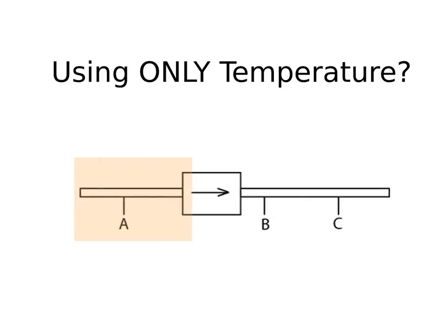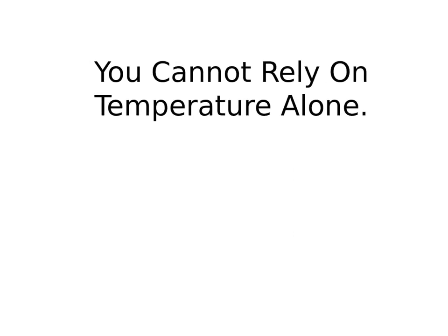If it's lower than 225°F, there's either a problem or that part of the steam system is not in service. Conversely, if the trap is hotter than expected, go to the downstream side and listen with contact ultrasound — you'd expect to hear nothing. If it's hot at the trap and quiet downstream, the trap is likely working just fine. But you can't rely on temperature alone, since back pressure may exist in the system.